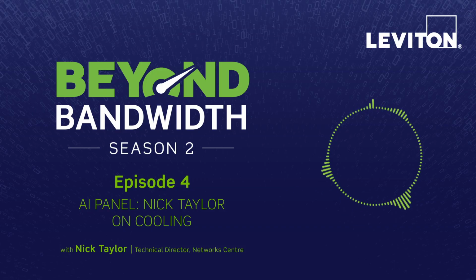Hot aisle. So hot aisle containment is what the vast majority of new data centers are in the UK anyway, and I guess probably around the world. There's usually not a raised access floor, although there could be. It's normally a slab floor. The cabinets go directly on the slab floor. All of the pathways for power and data are overhead. The cold air can come into the room in a number of ways, but generally in the larger data centers, it's an entire wall at one end of the room where the air is just pumped into the room. So it goes through the racks, up through a unichimney, so a single chimney that works for 2 rows of racks, usually up into the ceiling plenum and then back to the units outside. In certain locations around the world, it's free air cooling, so the air is literally pumped in from the outside of the building, with some humidity control with that.